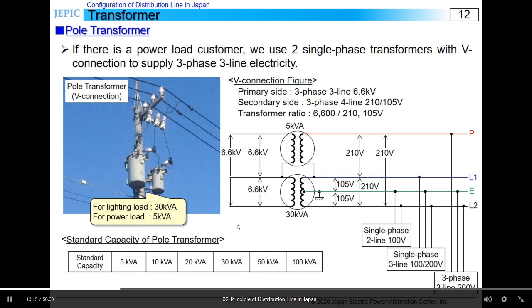The low voltage distribution system is three-phase 4-line. Drop service wire is connected to the low voltage system according to the customer's type. The transformer for lighting load has an earth as shown in the figure. This earth is put in for prevention of abnormal voltage invading the low voltage line, which might cause electric shock to customers when the high voltage accidentally contacts the low voltage side.